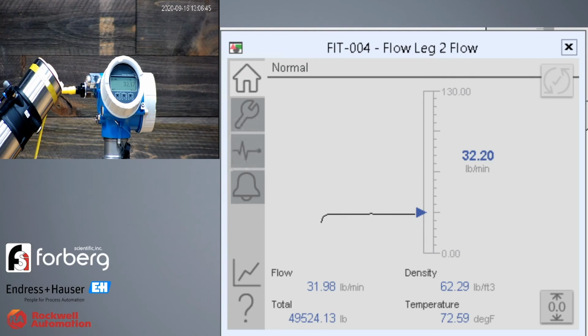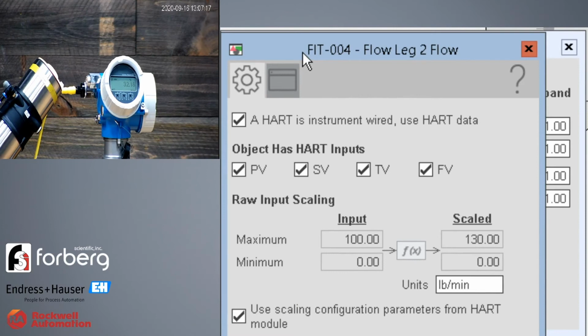Notice the four HART variables configured here: flow, a totalized flow value, density, and the temperature of the liquid. As I step through some of the engineering faceplates for this device, I want you to notice the device scaling, and the units are actually provided to the control system via HART. And please take note of the range of this device, 0 to 130 pounds per minute, as that number is going to come into play later on in this particular piece of the demo. So I want you to consider applications that if you're a control engineer, you could automatically adjust the engineering units on the process control PID loop when a process device is either replaced or a calibration range is changed in the field.